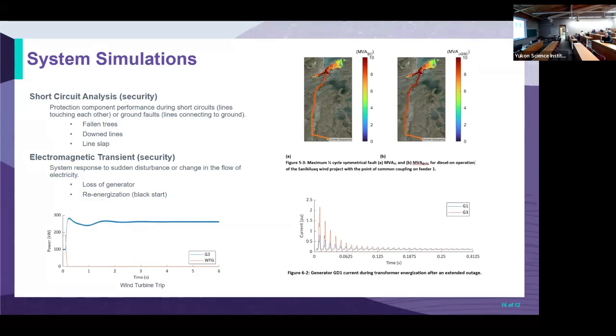The other system simulation is called the short circuit analysis. This checks what would happen to the system if something trips - for example, a tree falling on the transmission line, creating a short circuit. We can analyze how much short circuit current would occur, which helps us figure out the fuse size and protection settings for the thermal plant, the diesel generator.